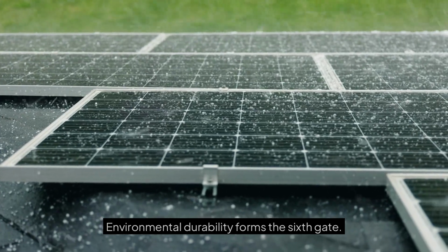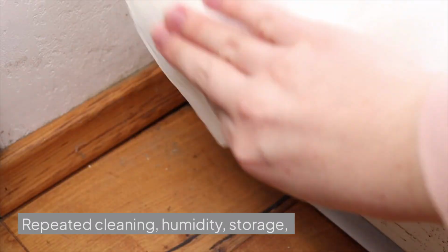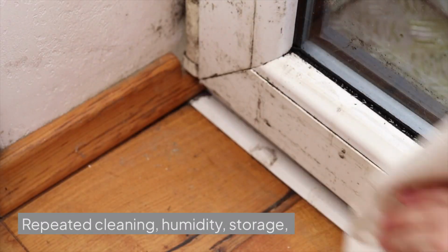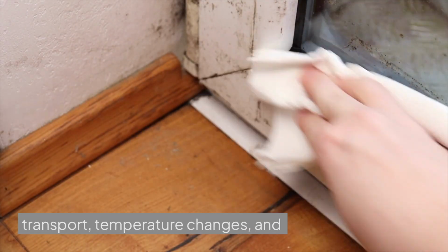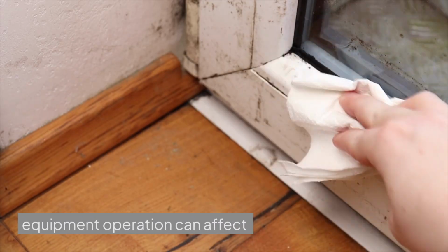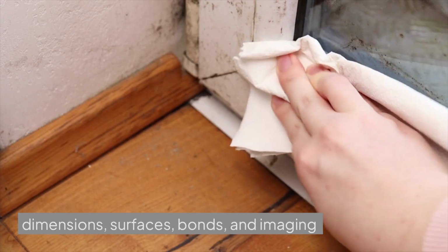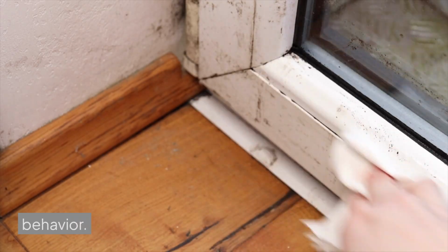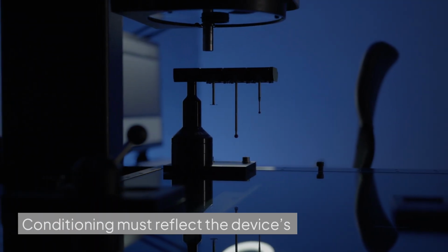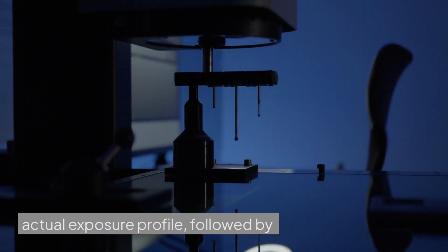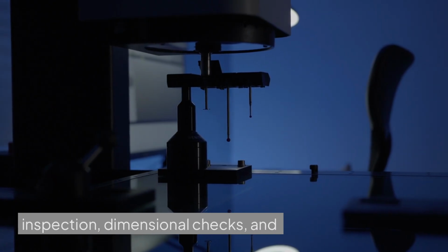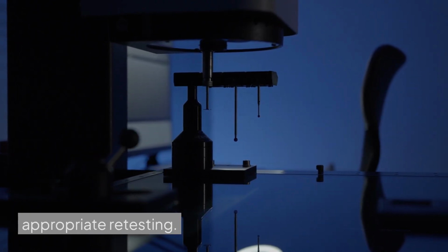Environmental durability forms the sixth gate. Repeated cleaning, humidity, storage, transport, temperature changes, and equipment operation can affect dimensions, surfaces, bonds, and imaging behavior. Conditioning must reflect the device's actual exposure profile, followed by inspection, dimensional checks, and appropriate retesting.